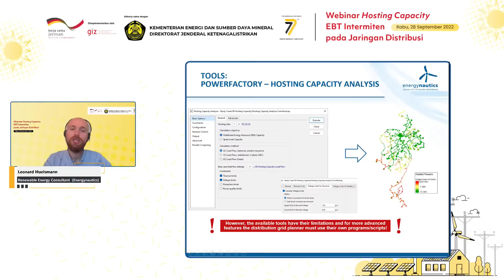Here is an example of such a tool, from DIgSILENT PowerFactory, where you can do such hosting capacity analysis and indicate how much PV capacity can be added where in the distribution network. Close to the substation it's a lot, and at the end of the feeder it's not as much.